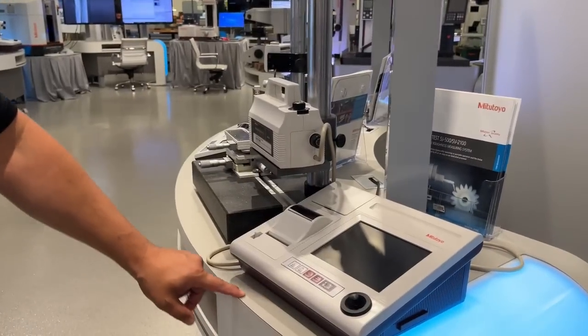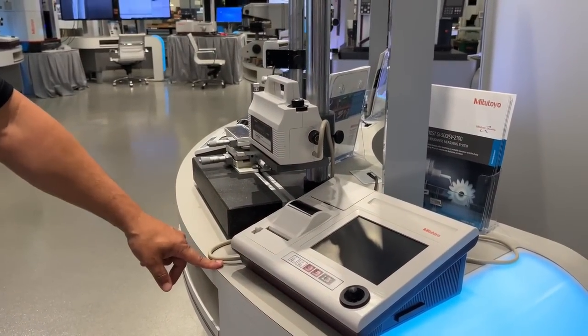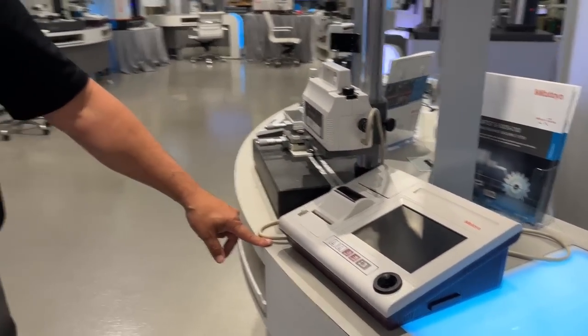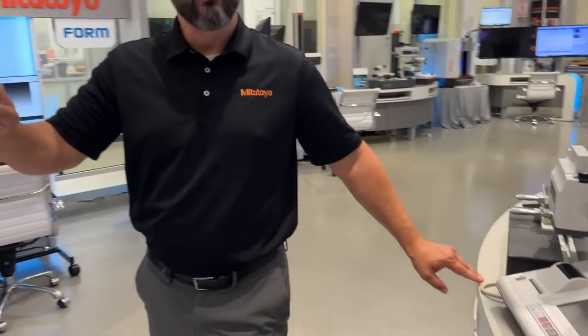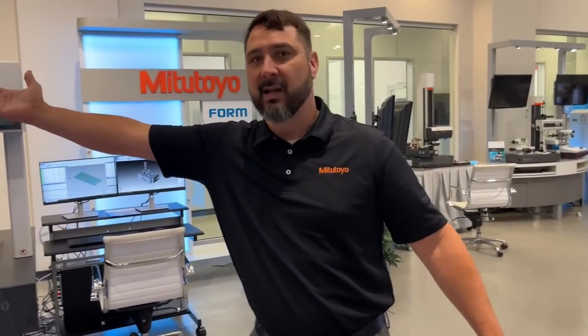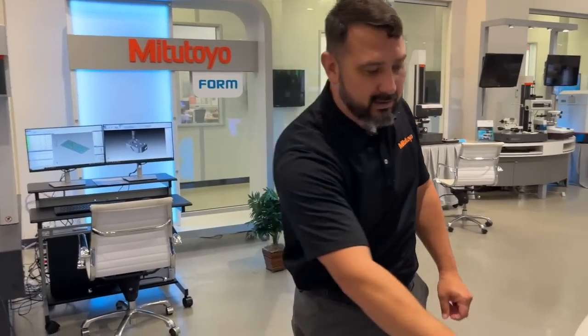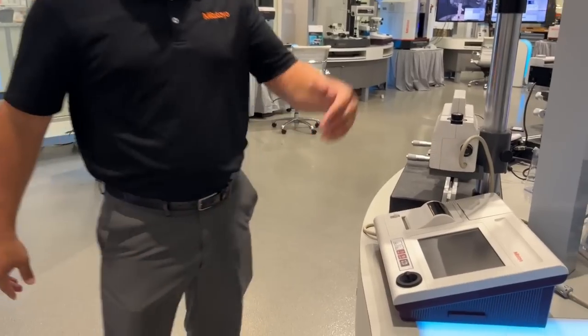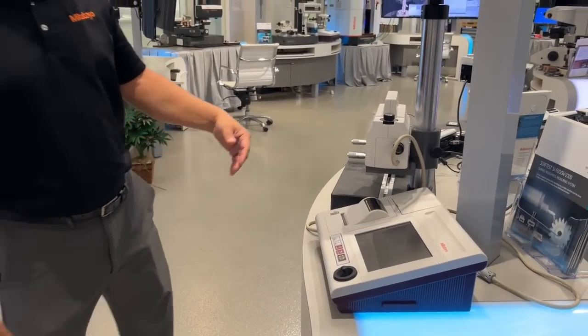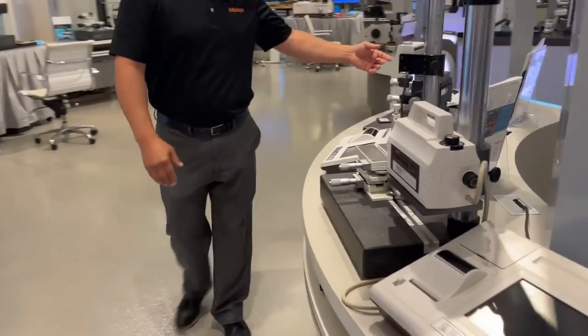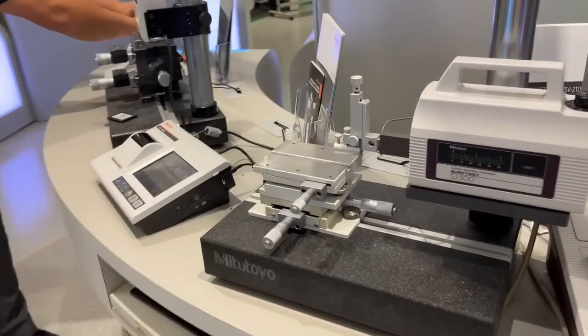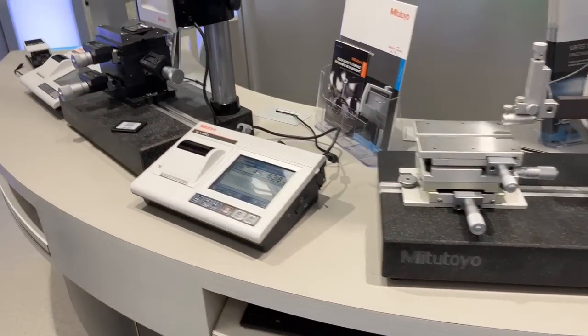Surface roughness testing. That's measuring the micro texture of a surface after it's machined. You're talking extremely small peaks and valleys in the sub-micron or millionths of an inch level. So the ruby ball on that CMM can never get you the resolution of that texture that you need. You can never see it with the camera. So there are many specialized pieces of equipment here called profilometers or roughness testers.